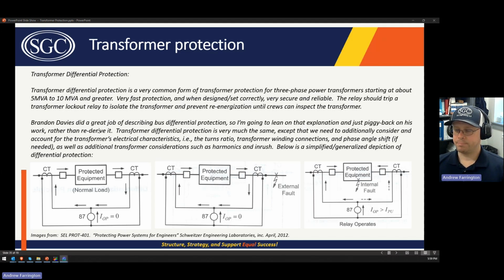At a high level, transformer differential protection is very similar to bus differential protection. It operates on Kirchhoff's current law. The amount of current through the transformer, when added together in a manner such as this, similar to bus differential relays, should equal 0 unless there's a problem inside the zone of protection, i.e. there's a transformer fault.